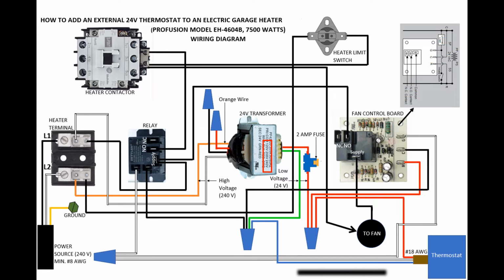In our case, since we have 240 volts coming in, we are going to use the white wire and the orange wire, which are connected to L1 and L2 of the terminals as shown. The other two wires, red and black, since we are not going to use them, you need to put caps on them, so end caps.